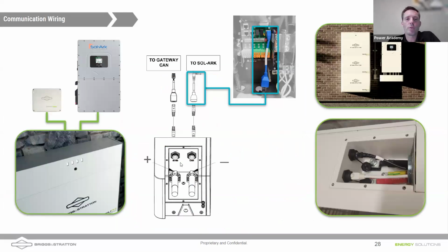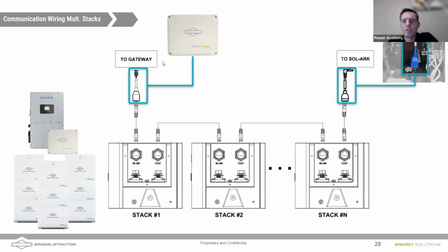You've got your power cable coming out of your battery controller, and then you have a single communications wire for a stack that would run through. We include this blue dongle with the stack controller of the batteries when you buy that. And then there's an additional Ethernet cable that would run into our gateway. And Daniel just went through wiring parallel stacks yesterday. So if you're wiring parallel stacks, it looks something like this.